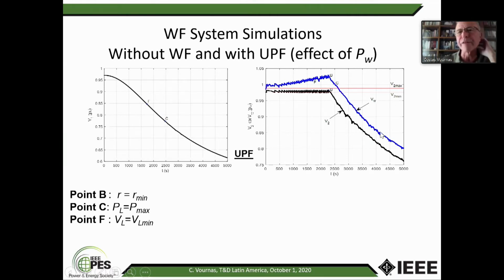You see how the unity power factor works in the right-hand side. This is the voltage of the distribution side of the transformer. And you see that this is kept constant by the tap changer with ups and downs, because when it goes out, then the tap changes. And this is the voltage of the wind farm, and you see it's varying with the wind and increasing, because more is required from the feeder to keep the unity power factor. And after you reach point B, where your tap changer can no longer control the substation distribution voltage, the voltage drops in both cases.